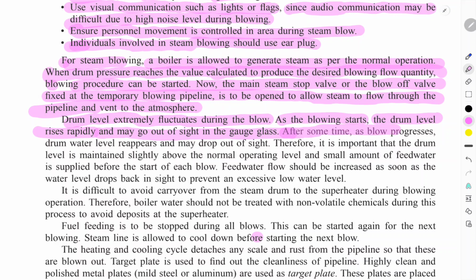After some time, as the blowing progresses, the drum level may drop slightly. Therefore, it is important that the drum level is maintained slightly above the normal operating level. A small amount of feed water is supplied before the start of each blowing. The feed water flow should be increased as soon as the water level drops back slightly, to prevent excessively low water level. Low water level must not be allowed during the blowing.